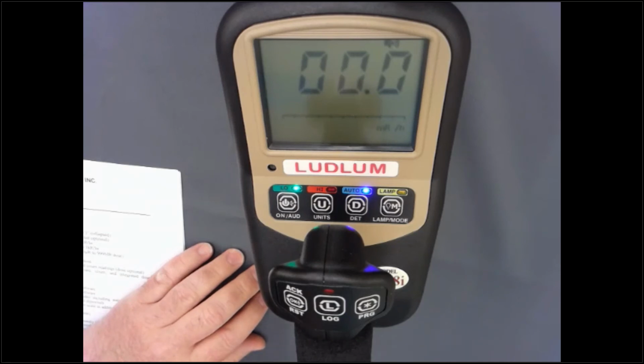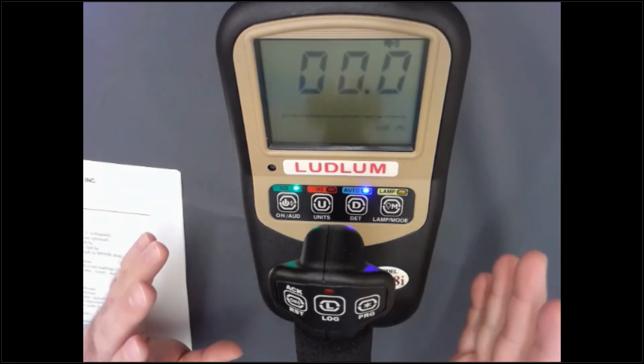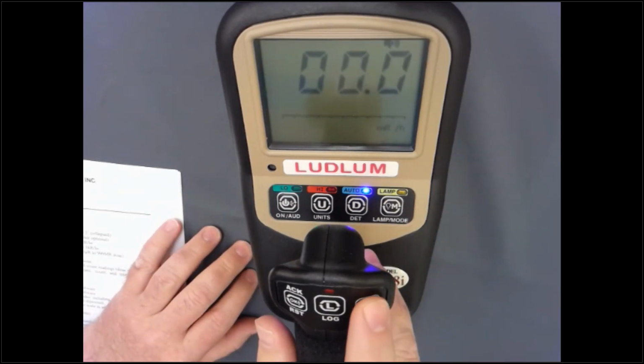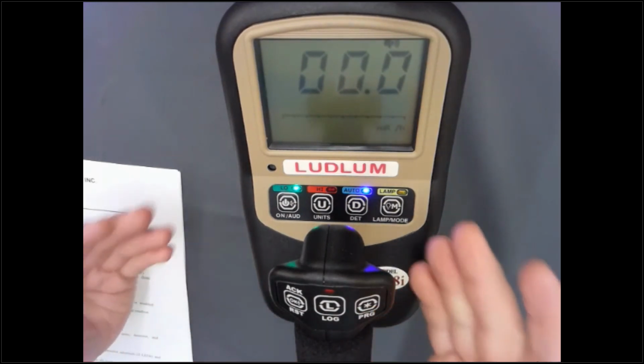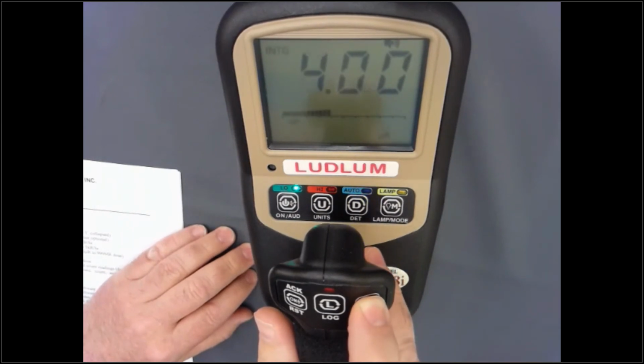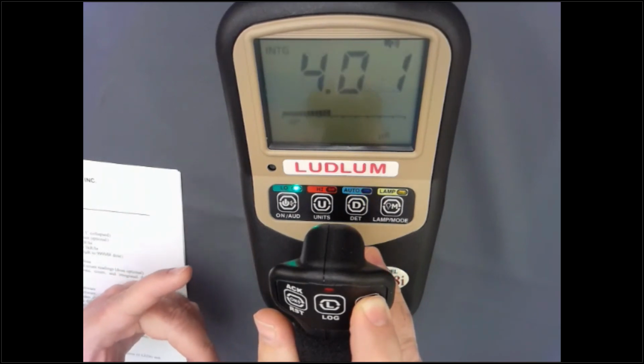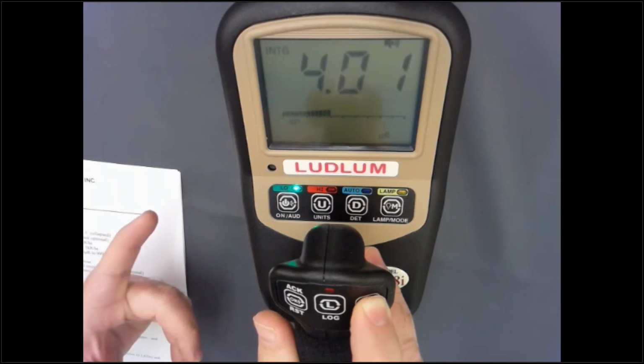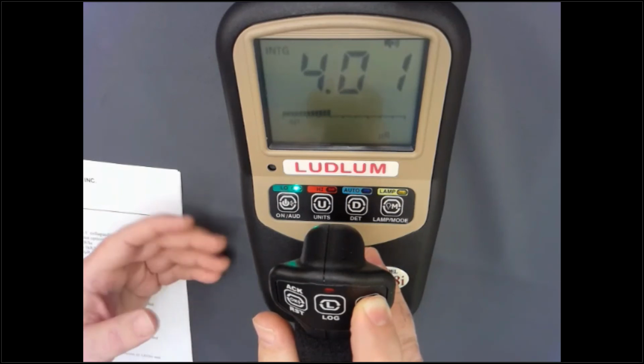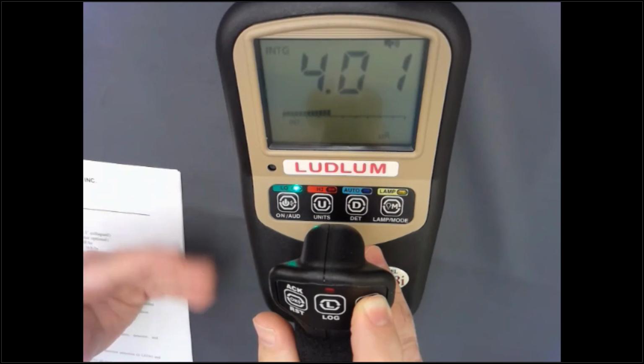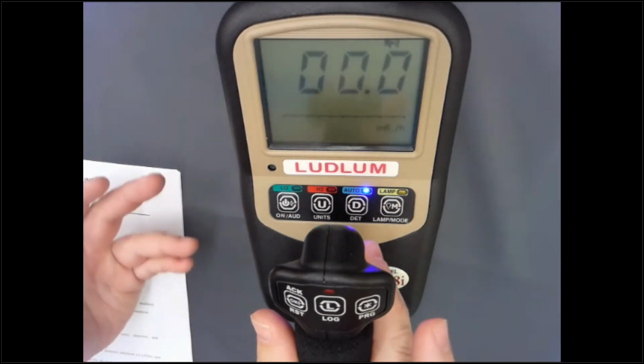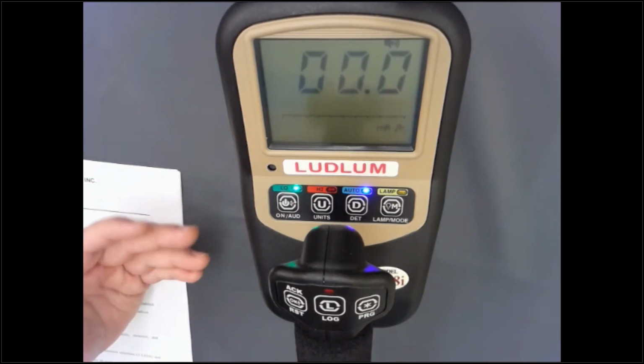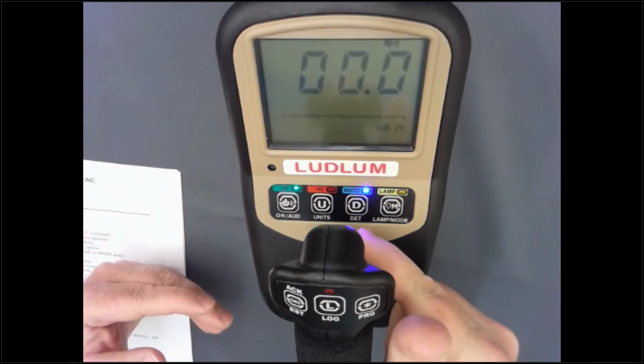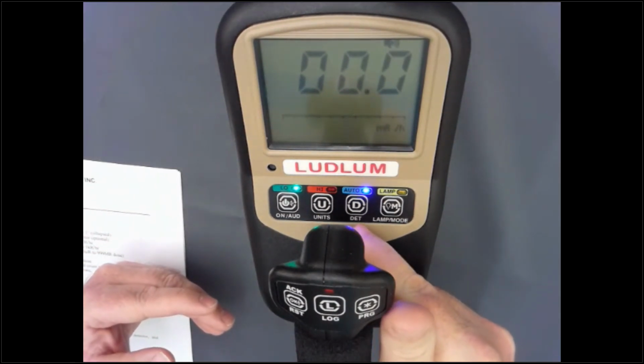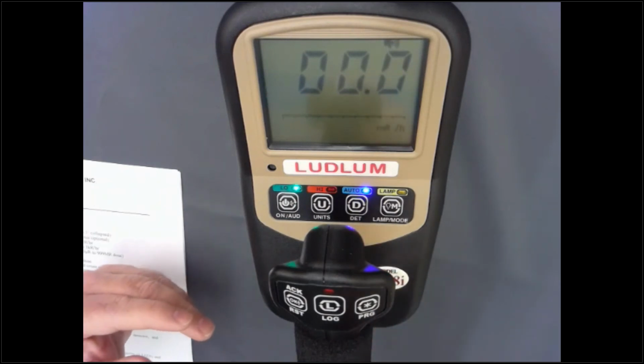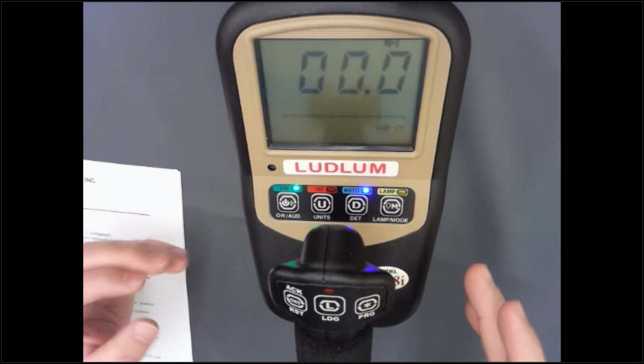Another feature with this instrument is when we're up and running, we can use the program button. When we're looking at the external detector, the program button is a quick way to just switch over and view what's going on in the internal detector in the integrate mode. So if you want to see what your dose is while you're operating an instrument, just press and release it, and it immediately goes back to the external detector. Or you can switch to the internal detector by holding the detector button for 2 seconds, 3 beeps, and it will actually lock it into the internal detector mode.